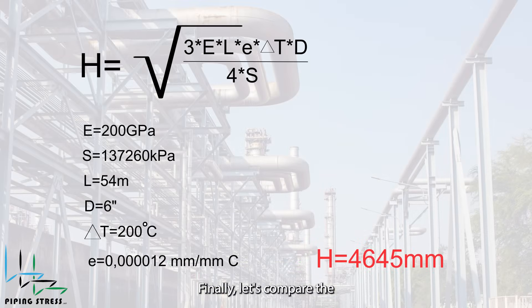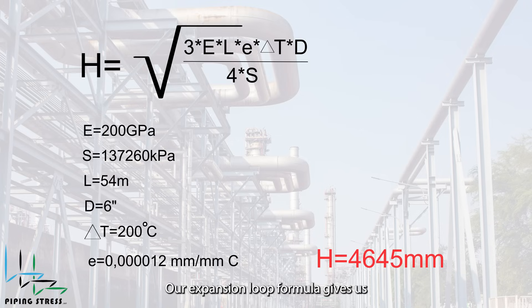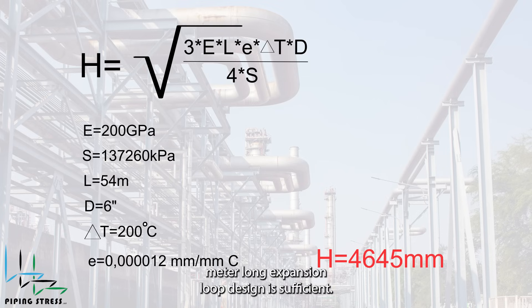Finally, let's compare the hand calculation with our design. In our CAESAR II model, we designed the expansion loop with 6 meters long. Our expansion loop formula gives us 4.6 meters. So, the 6-meter long expansion loop design is sufficient.